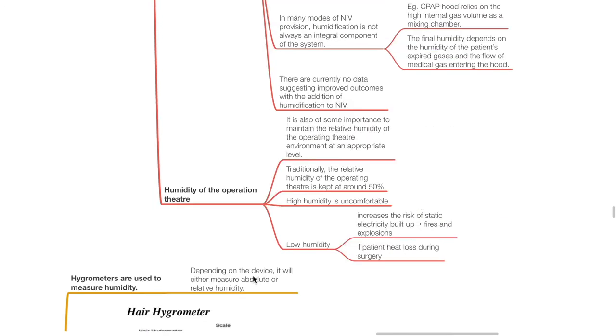Humidity of the operating theater. It is important to maintain the relative humidity of the operating theater environment at an appropriate level; traditionally the relative humidity is kept around 50%. High humidity is uncomfortable. Low humidity increases the risk of static electricity build-up, which increases the risk of fires and explosions and increases patient heat loss during surgery.